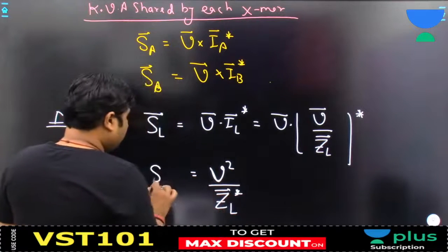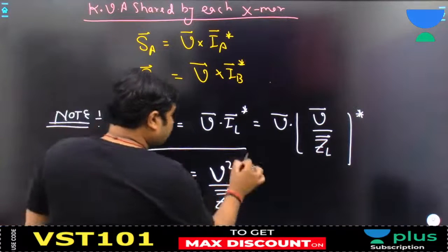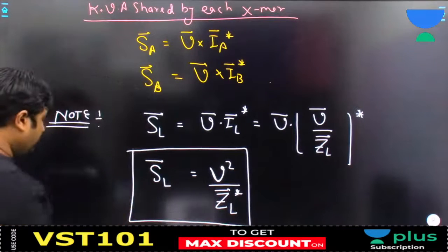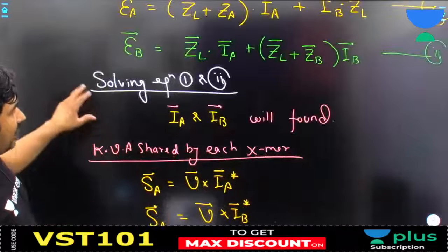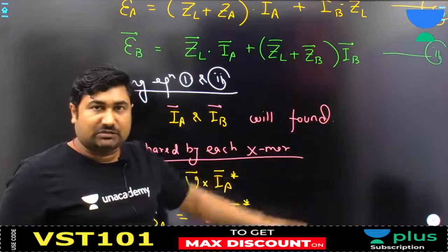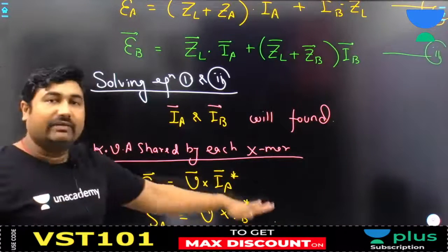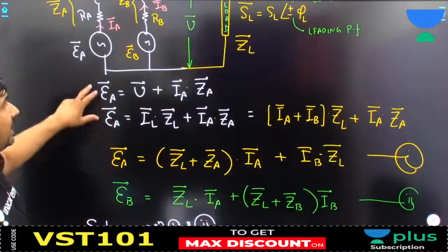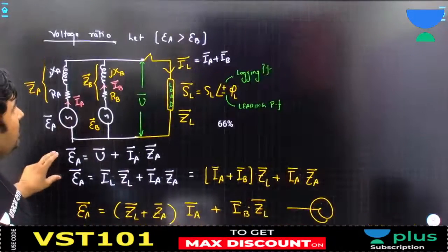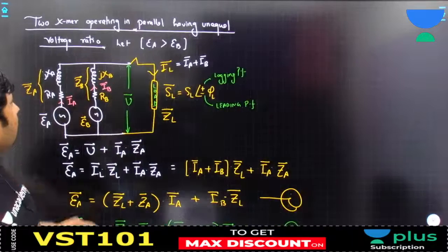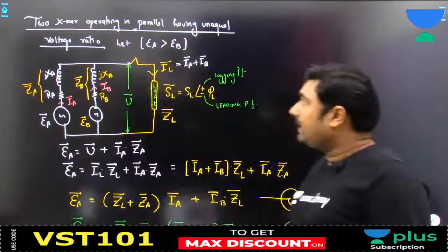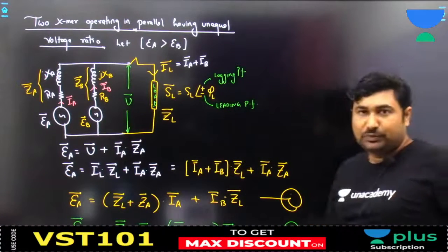So if you know about SL, you can calculate ZL from this, and then proceed for finding current delivered by each transformer when operating in parallel, and KVA delivered by each transformer when operating in parallel. Are you able to understand up to this part, the two transformers operating in parallel having unequal voltage ratio?